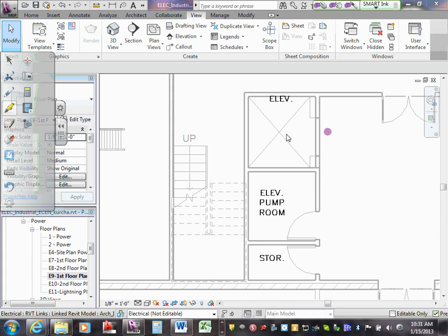Not unless they have it sprinkled, and they're going quick. The code says they do not want any sprinklers in the elevator shafts or even in the elevator room. Otherwise, you have to have a heat detector in there, shunt trip all the equipment before the sprinkler goes off, and have a high temperature sprinkler in there, and a heat detector that's rated for 15 degrees below that sprinkler. They got away with all that, thankfully. You need a heat detector here, no, only if it's sprinkled. If there are sprinklers in the elevator shaft, then you have to have one in there. But typically, nowadays, the code does not require them, and fire marshals and elevator inspectors don't want to see those.